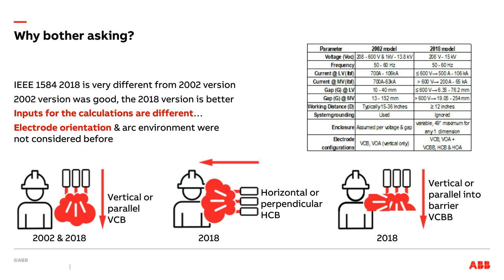Okay, so what are the changes? There's several. Probably the single most important one is that in the old model, all the tests, all the data that was used to create the model was based on the conductors that caused the arc flash, that held the arc, being parallel to the worker. The term used in the documents is vertical, but in reality what it means is that the bus bars, cables, the source of the electrical energy is parallel to the worker. It's kind of like looking at a train that's going by you. Now somebody could throw something out the window of that train and hit you, and the speed of the train and how much stuff they throw at you will have impact, but the train is not going to hit you because it's going by you.